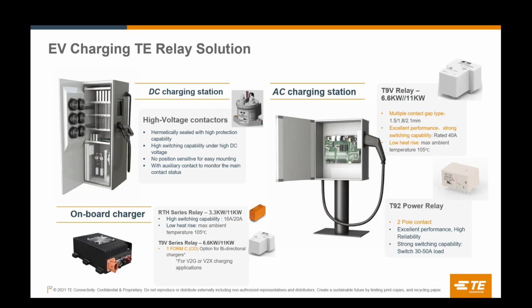Level 2 would be the units you might have installed in your garage, or installed outside a commercial establishment or office. Level 2 has 3 subgroups as we see it now. On the low end, a 7 kilowatt unit that pulls about 32 amps at 240 volts AC, and our T9V relay is ideal for that. Two of those should take care of this 7 kilowatt application.